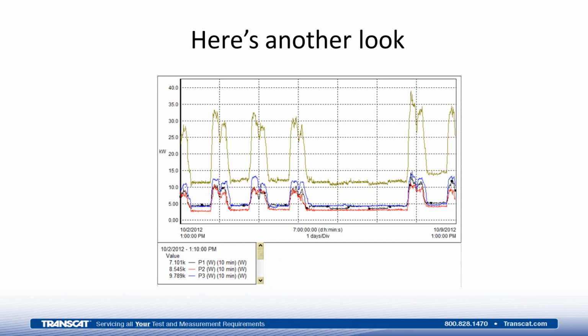In an industrial or larger commercial sectors, they will use a different form of metering, anything from what is called a VAR compensating meter to other techniques, and they will bill you for additional things other than the energy usage. You could succumb to a peak charge. You could succumb to a power factor charge. There's even discussion in the industry about billing you if your facility is generating harmonics. All this occurs in the industrial and the commercial sector, does not occur in the residential sector. So if you're doing residential monitoring, you have to do a lot less to understand your energy bill. When you're in the commercial or industrial sector, you have to do significantly more to understand your electrical energy bill.